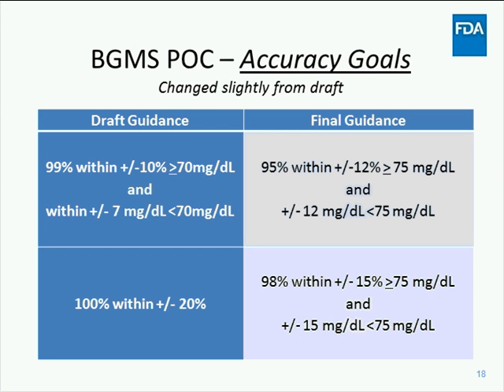Now, the accuracy goals that are described in the BGMS guidance for point-of-care use have changed slightly since the draft guidance and have been loosened some based on comments we received on the draft. The draft stated that 99% of meter results should be within 10% of the comparator method for glucose concentrations greater than 70 and plus or minus 7 mg per deciliter for glucose concentrations less than 70, and that 100% of values should be within 20%. This final guidance now states that 95% of the meter results should be within 12% for glucose concentrations greater than 75 or within 12 mg per deciliter for concentrations less than 75, and that 98% instead of 100% of the meter results should be within 15% or 15 mg per deciliter of the comparator method.